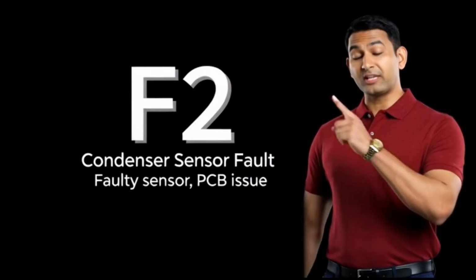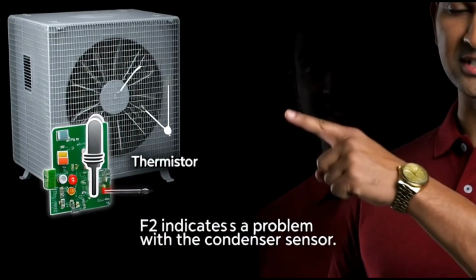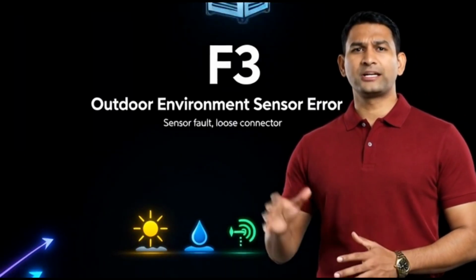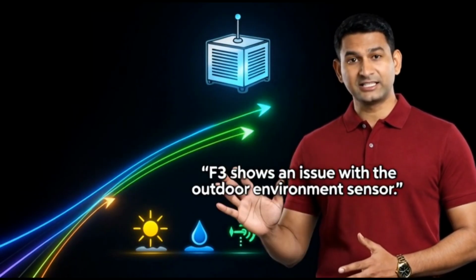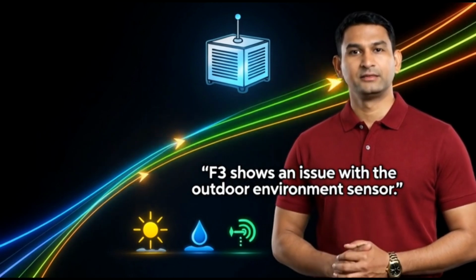F2 indicates a problem with the condenser sensor. This is caused by a faulty sensor or PCB issue. The reading is unstable. F3 shows an issue with the outdoor environment sensor. This sensor fault is caused by a loose connector.